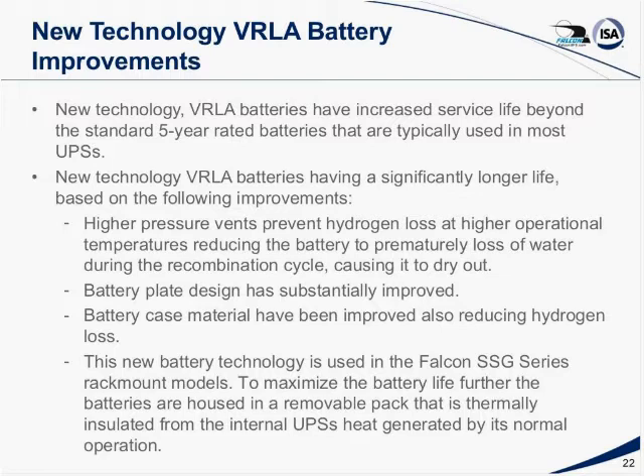The other difference is plate design. There's a substantial improvement in plate design. The plates are better supported, so the temperatures don't tend to buckle the plates in the batteries. The battery case material is improved. Some plastics can actually pass hydrogen. The terminal connections and the adhesives that are used to seal the case can improve or degrade the battery life and increase or decrease hydrogen loss.